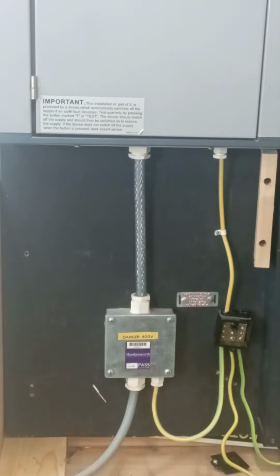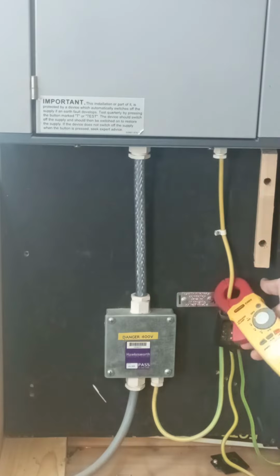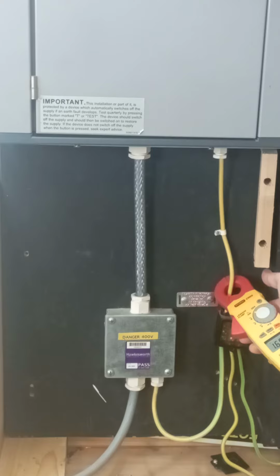Right guys, prior to our controlled shutdown with the installation energised, one of the things we should do is check for earth leakage currents and any diverted neutral conductor currents. So first thing we do is check the circuit protective conductor leaving the main earthing terminal to see if we'll get any current circulating in that conductor.